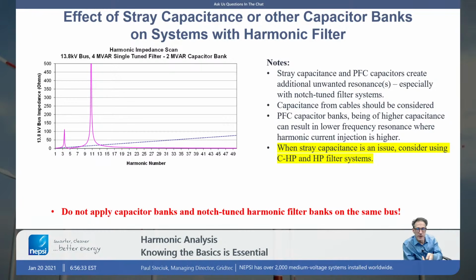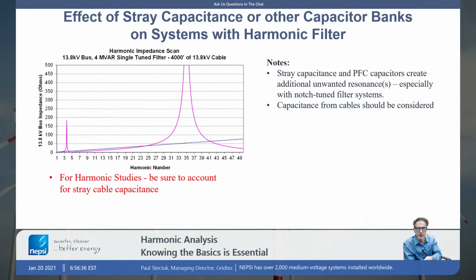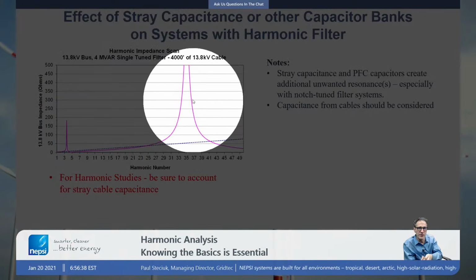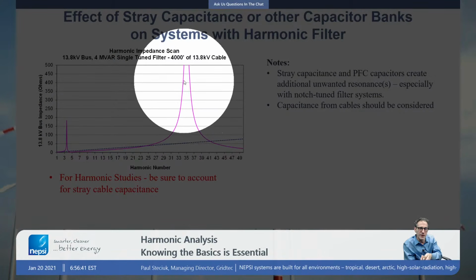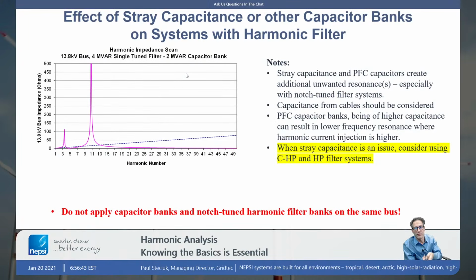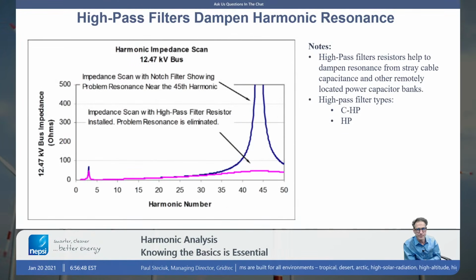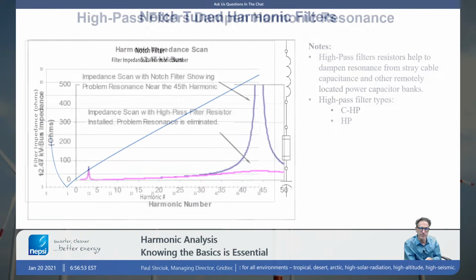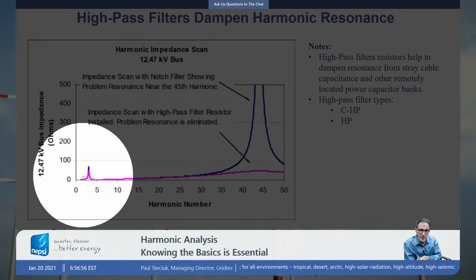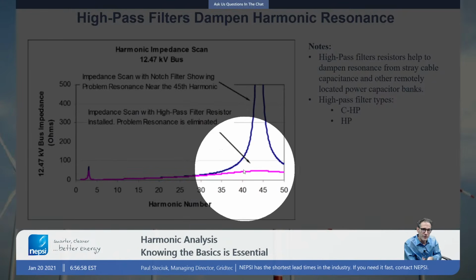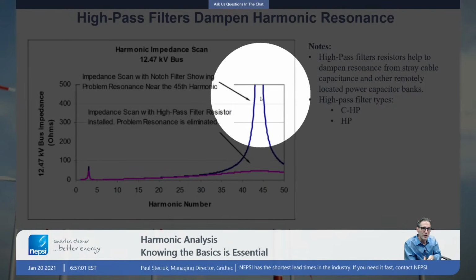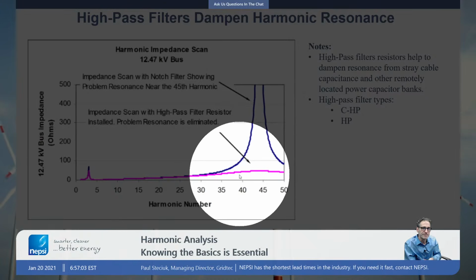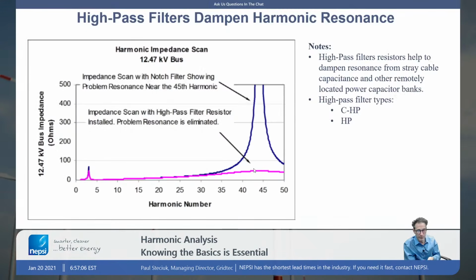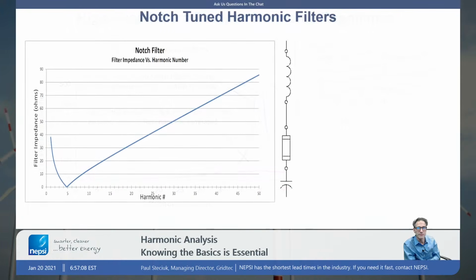Okay, so in systems, in particular in systems like this, you see this in renewables, we have this cable capacitance. We would go with a type of filter called C-high pass or high pass filter. It's a damped harmonic filter. And that's what we're showing here, incidentally. I've taken a notch filter and I've added that notch filter as a high pass filter, and you can see I can eliminate that resonant peak there by putting a resistor basically across the reactor.